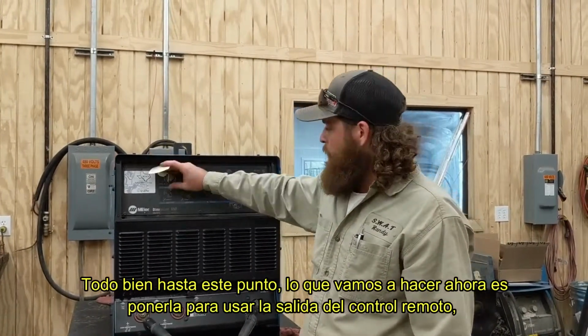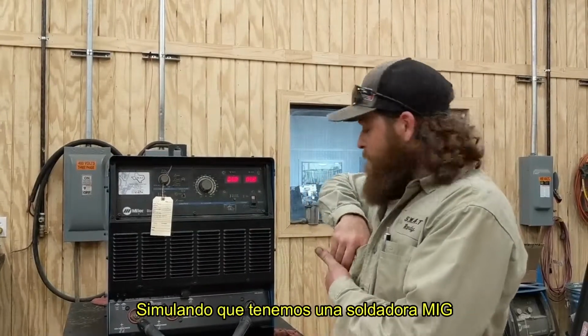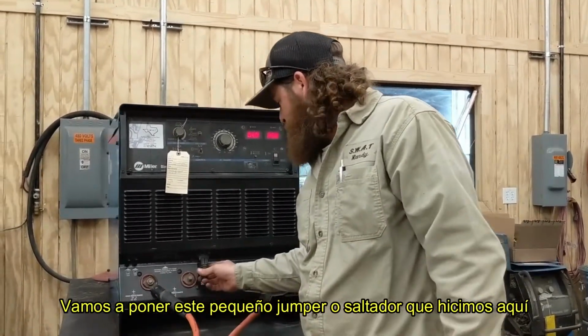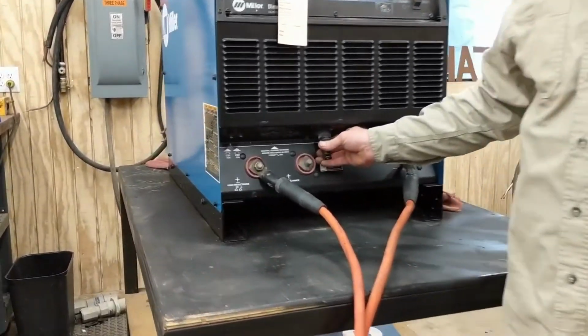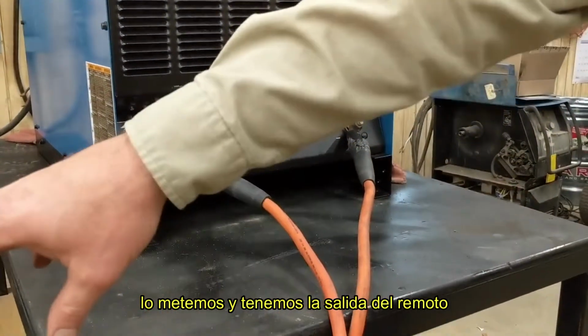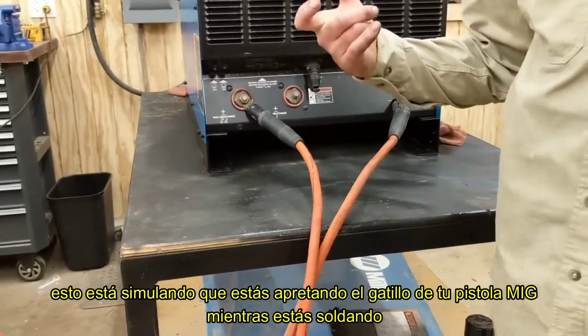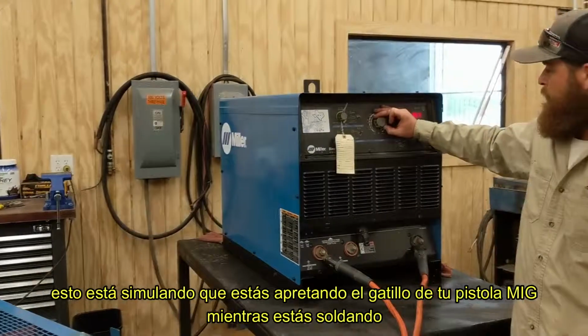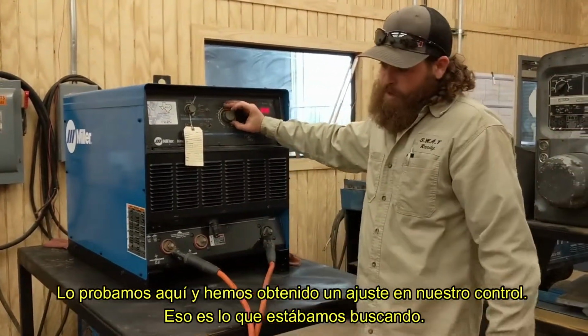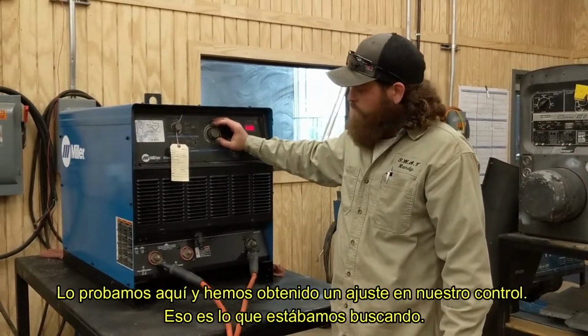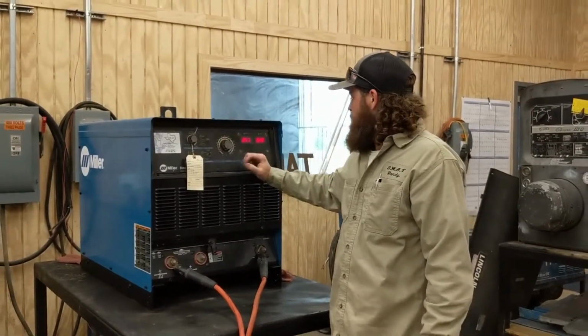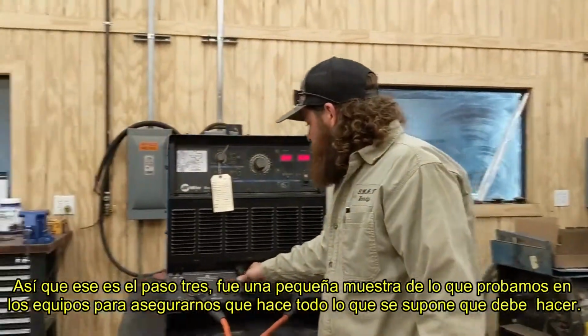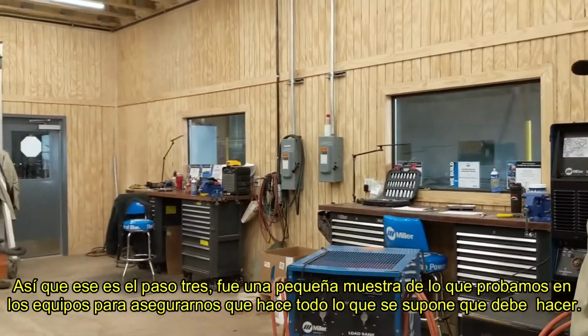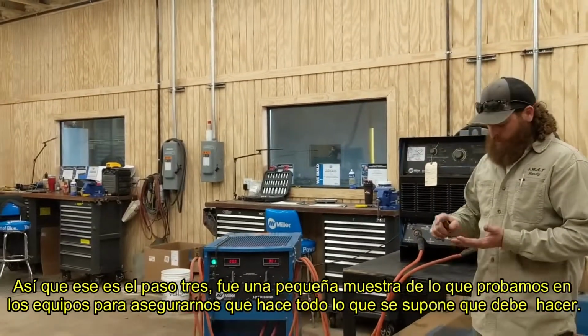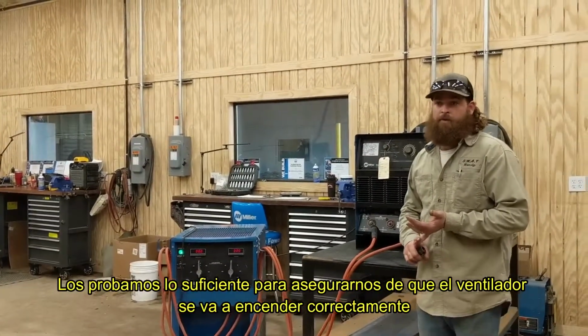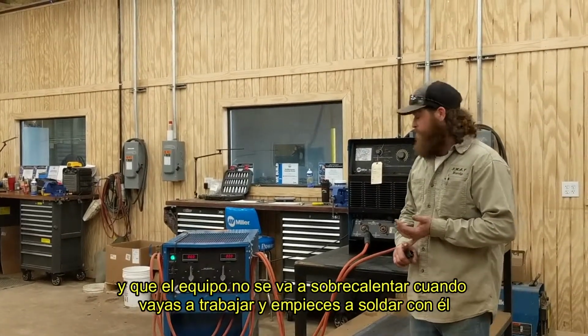The next step we're going to do is flip it over to the remote output. Simulate you having a MIG welder. Take this nice little jumper we've made here. Plug this little guy in. We have remote output. This is simulating you sitting there squeezing a trigger on your MIG gun while you are welding. If you want to test it here, we've got adjustment in our remote. That's what we're looking for. So that is step 3, the load bank. We test this guy to make sure it is going to do everything it's supposed to. We run them long enough to make sure the fan is going to come on, that way it's not going to overheat when you get out on the job and start welding with it.